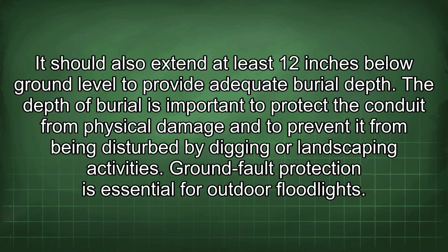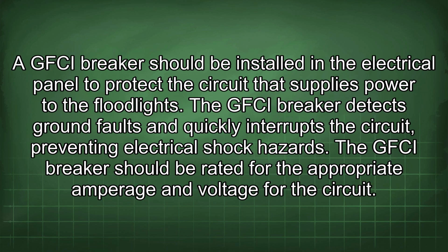The depth of burial is important to protect the conduit from physical damage and to prevent it from being disturbed by digging or landscaping activities. Ground fault protection is essential for outdoor floodlights. A GFCI breaker should be installed in the electrical panel to protect the circuit that supplies power to the floodlights.